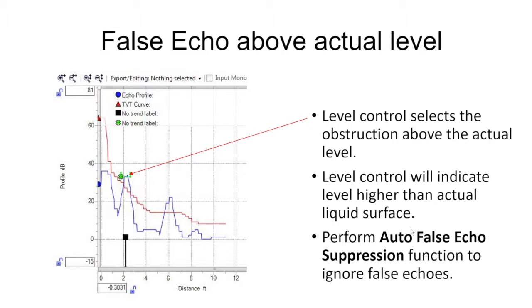Here's an example of an echo profile showing a false obstruction above the actual level. In this particular one at six feet we have a good echo at the actual level, but at two feet I'm getting a strong echo that is higher than our red TVT line, so the radar gauge selects that as our true echo.